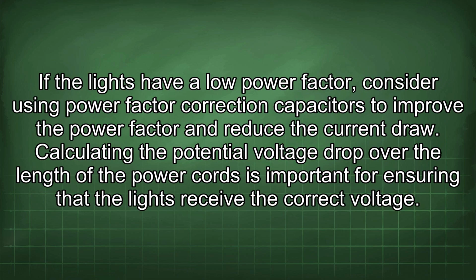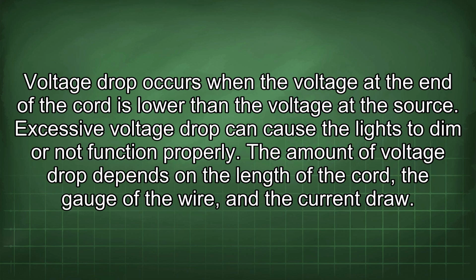If the lights have a low power factor, consider using power factor correction capacitors to improve the power factor and reduce the current draw. Calculating the potential voltage drop over the length of the power cords is important for ensuring that the lights receive the correct voltage. Voltage drop occurs when the voltage at the end of the cord is lower than the voltage at the source.